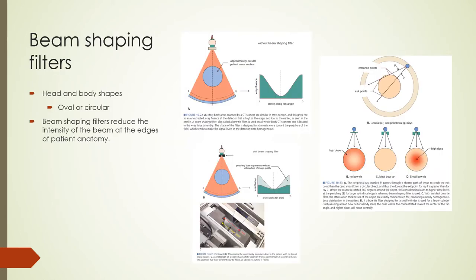Most CT scans are of the head and torso area, divided into chest, abdomen, and pelvis. These anatomies are oval or circular in shape and attenuate the X-ray beam to different extents. To account for this uneven attenuation, manufacturers use beam shaping filters — called bow tie filters — to equalize the beam over the face of the detector. Figures show the beam profile without the filter, the effect of the filter on flattening the beam, and scenarios with no bow tie, an ideal bow tie, and a small bow tie filter.